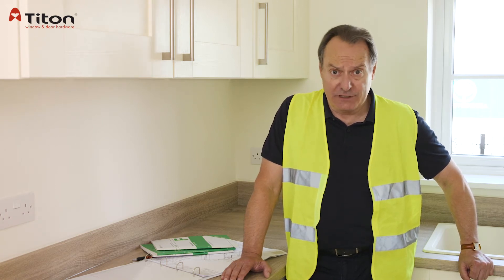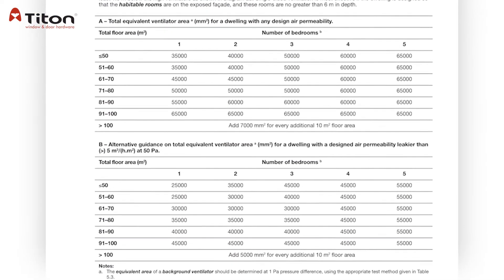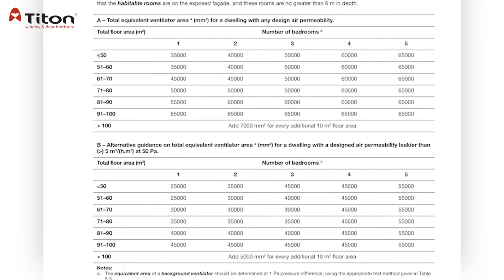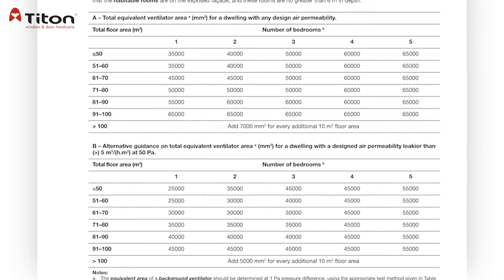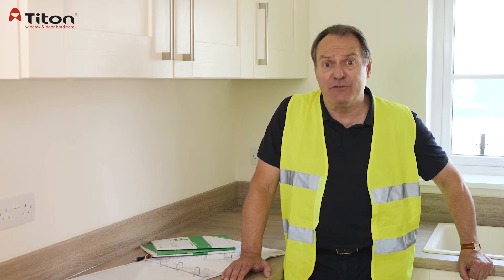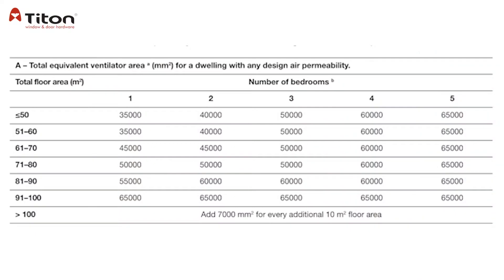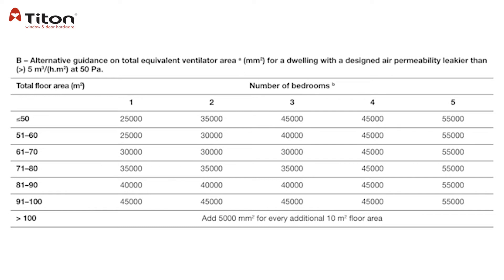The first thing that has to be established before checks can be made is the air tightness level of the property, as Part F uses two different tables to calculate the background ventilation requirement according to the air permeability. Air permeability is checked at 50 Pascals. If it's not known, or tighter than 5 metres cubed per hour per square metre of floor area, then this table is to be referenced. If it's greater — leakier than 5 metres cubed per hour per square metre of floor area — then it's this one, which doesn't require as much background ventilation.